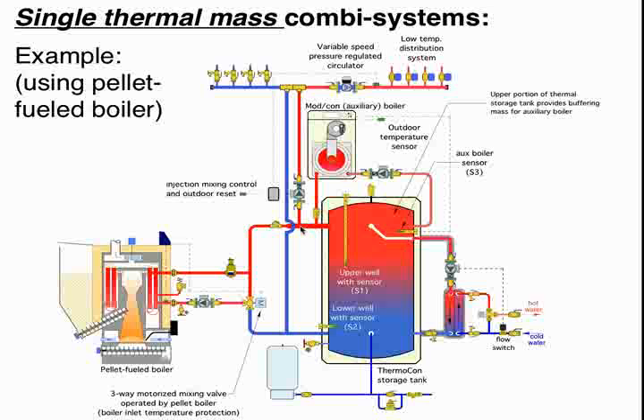Now, the key thing with a 2-pipe buffer is to keep the T's that go off to the load as close as possible to the tank. And you can still see that schematic. What we're looking at is the pressure drop from this T, where the load tees off from the, I'll call it the upper tank inlet header, and then down through the tank itself has very low pressure drop, almost insignificant. So as long as we keep these T's that connect to the load close to the buffer tank, a 2-pipe configuration will still provide hydraulic separation.